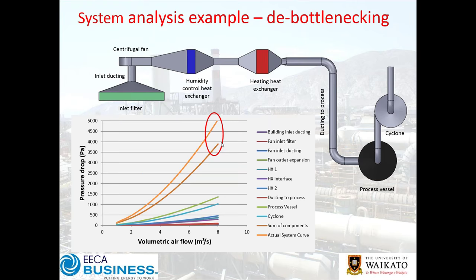After addressing the system effect, the next focus is the process vessel and cyclone, which have relatively high static pressures. The question is: is that expected? It could be the cyclone is meant to operate that way and is actually working properly. What you'll typically find is that the system effect and the entrance and exit effects of the cyclone are closely tied. Lastly there might be smaller opportunities — is the filter bank being kept clean, or is it higher than it should be? Housekeeping bits and pieces matter.